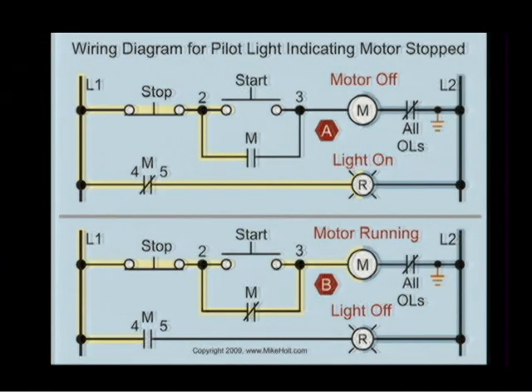But hold on. If that were the case, using this previous example, if I press the start button, I energize the coil, right? I now close the contacts. The motor is running. I press the stop button. I de-energize the coil. The light then comes back on, right? Indicating the motor has stopped, but in reality, the motor is still running. That can happen, yes. And that's a danger that we're saying. You've got to be careful. You can't depend on lights to tell you whether something is operating or not operating.